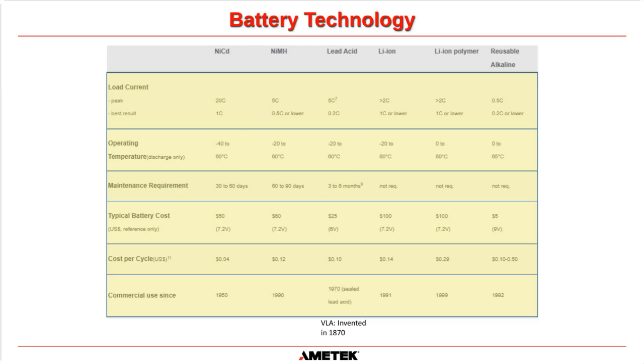So for a lead acid battery, they are extremely temperature sensitive. They want to be charged at 20 degrees C, which is actually 25 degrees C, which is 77 degrees Fahrenheit. Okay, that is what a lead acid battery wants. NiCads really, although you do have to adjust the float voltage to the temperature, they're very tolerant to cold temperatures or warm temperatures. Very, very tolerant indeed. It's not going to cause any damage to the battery, really, in any shape or form.